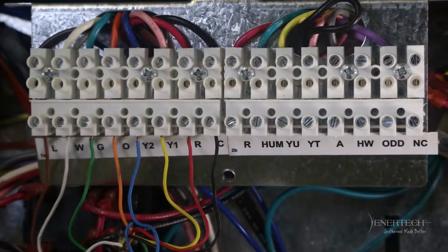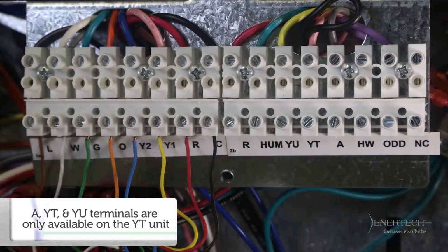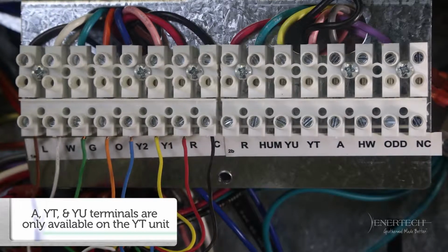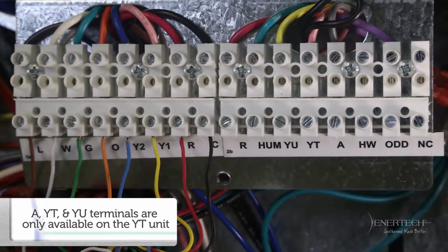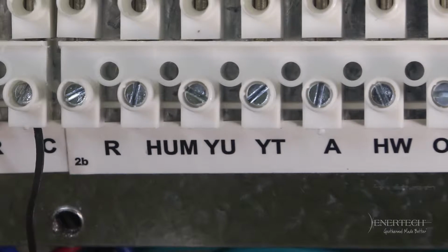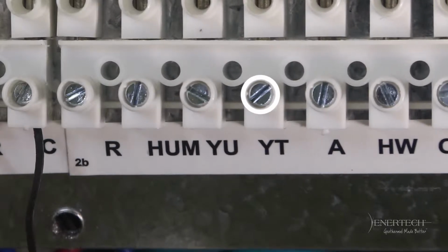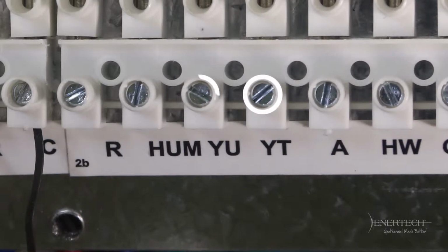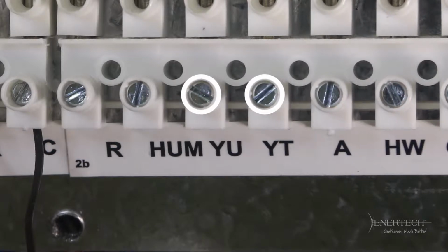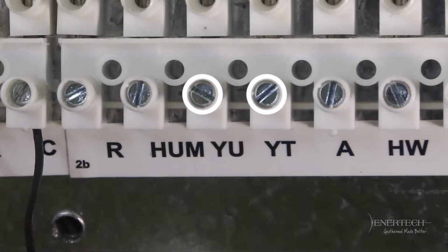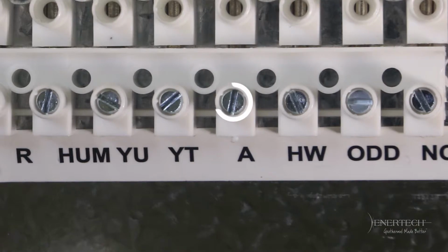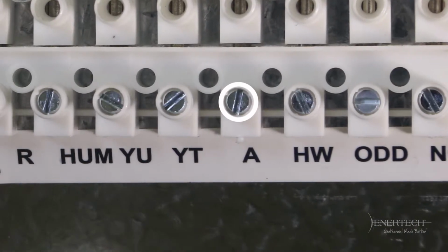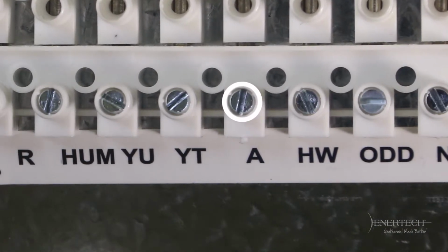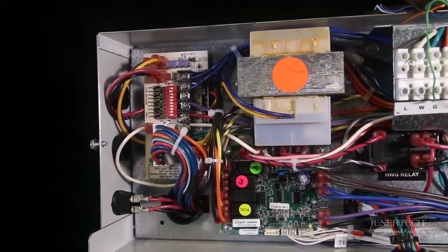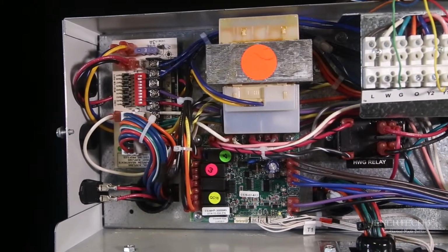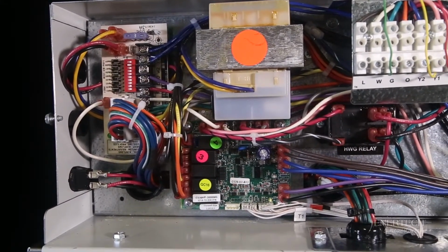When provided, the YT and YU terminals on the accessory terminal strip provide a field connection for a valve with an end switch, which is recommended. The YT terminal can be used to power the solenoid valve and end switch. The YU terminal can be powered through the end switch and connects internally to the Y circuit of the unit controls. An accessory relay terminal A can be used for solenoid valves without an end switch. This terminal is energized 10 seconds before the compressor contactor. A valve without an end switch could cause a water hammer issue and is not recommended.